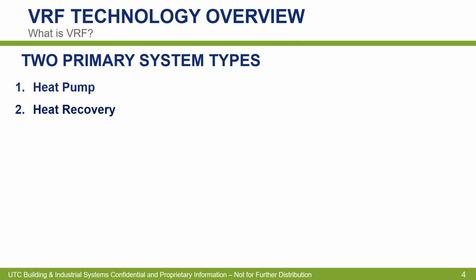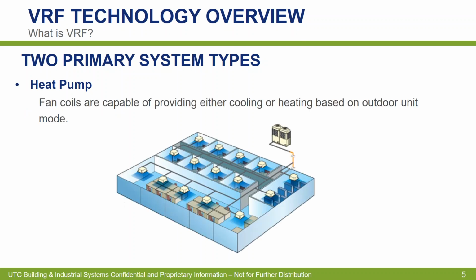So two primary systems when it comes to VRF: heat pump and heat recovery. We're all familiar with the heat pump technology, and that, hey, the system's going to be either in cooling or it's going to be in heating. It can't be in both. If you want both, we go to heat recovery, and we'll get deeper into that as we go through the slides here.